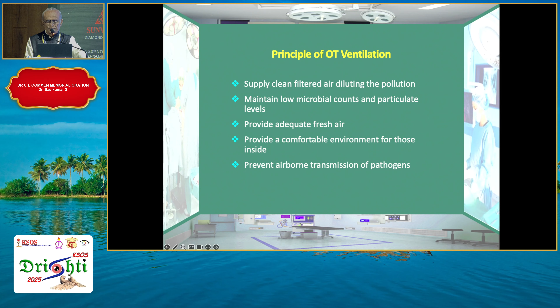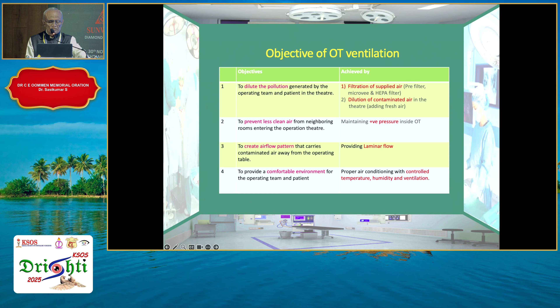To prevent less clean air from neighboring rooms from entering the operation theater, positive pressure is maintained inside the OT. To create an airflow pattern that carries contaminated air away from the operation table, laminar flow is provided. And to provide a comfortable environment for the operating team, proper air conditioning is given, with controlled temperature, humidity, and ventilation.